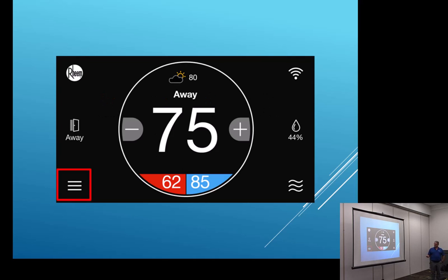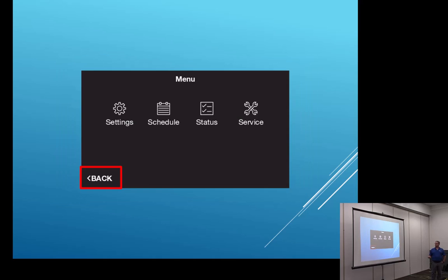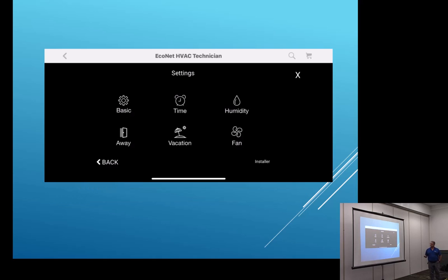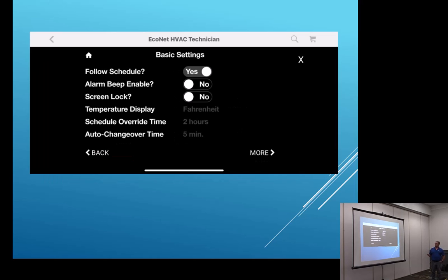This is our menu button down here. We call it the little hamburger symbol. And it brings us to our menu settings, schedule, status, and service. In settings, we have our basic here. Basic settings, follow schedule. I had one where they changed the thermostat twice. And finally, my guy had to go out to the job site. He even took the controller with him just in case. He called me on the way, and I said, they've got to have a schedule running because it was just changing temperatures all the time by itself.